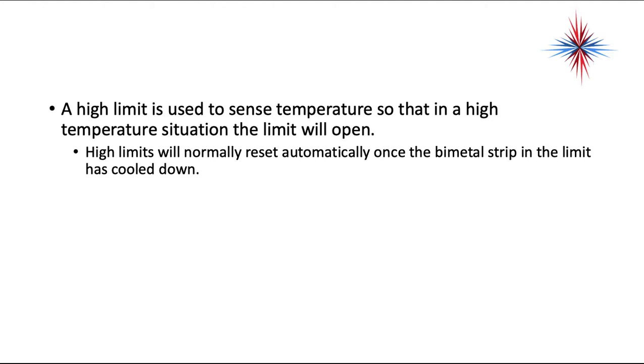A high limit is used to sense temperature so that in a high temperature situation, the limit will open. High limits will normally reset automatically once the bimetal strip in the limit has cooled down.